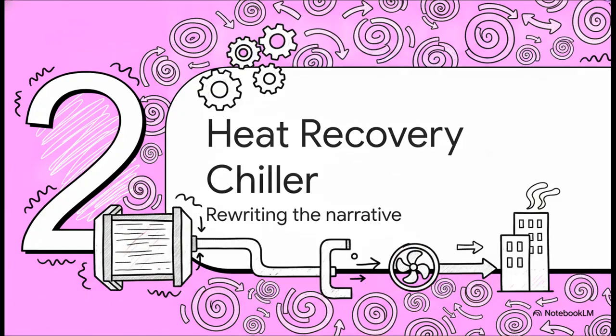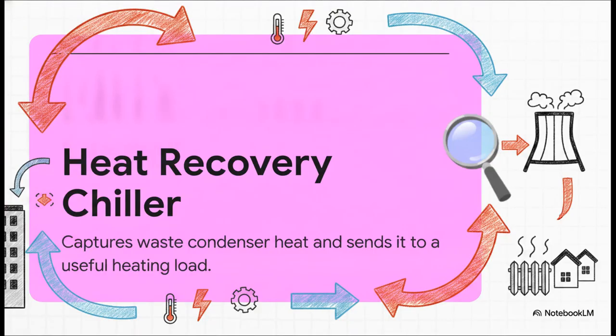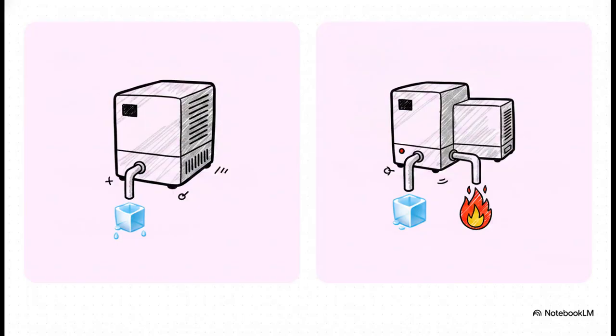Enter the heat recovery chiller. Enter the innovation that changes this whole story. So, what actually is it? Simply put, a heat recovery chiller is a system that captures condenser heat we normally treat as total garbage, and sends it to a useful heating load instead of just dumping it out of a cooling tower. The crucial takeaway here is that this machine doesn't just magically create heat out of thin air. Actually, scratch that. It's more like a traffic cop. It intelligently captures the heat that's already being removed from the building and just relocates it to exactly where it's needed. And this fundamental difference completely changes how we evaluate the equipment.